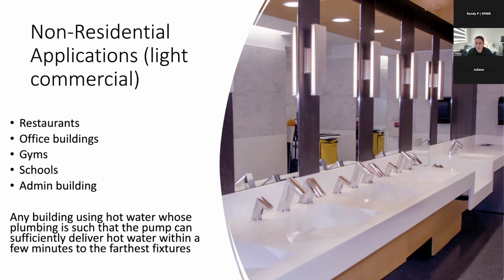If you've got an occupancy sensor in the back of the house, and maybe one in each of the lavatories, then that pump is going to stay off anytime there's nobody in that building, and then it's only going to stay on as long as it takes for the hot water to get through the loop. So just remember that if you have the occupancy sensors and people keep walking in front of the occupancy sensor, it doesn't mean that the pump keeps turning on, because as long as hot water is in the line, the pump will stay off.